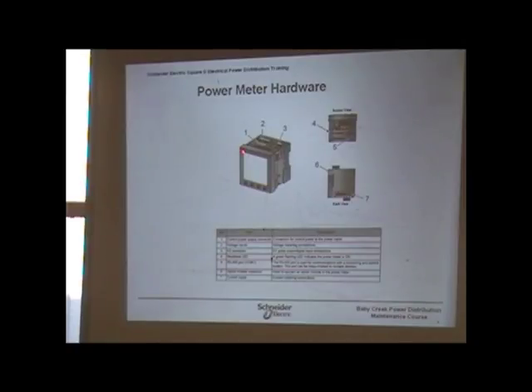So for control power, you could use a CPT or use one leg from your monitoring voltage, which would make it like 277 or something like that, and then a neutral. So essentially that's what you would use there, or it might combine to 120 if you were using control power, or 220 if you use 2 legs of control power.